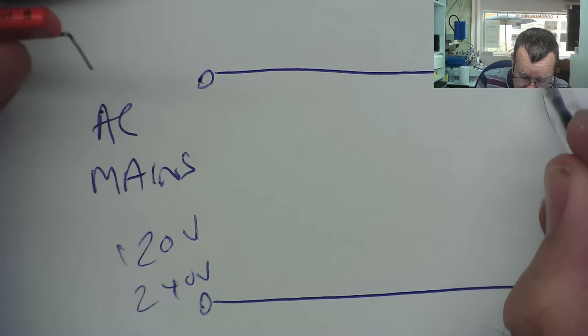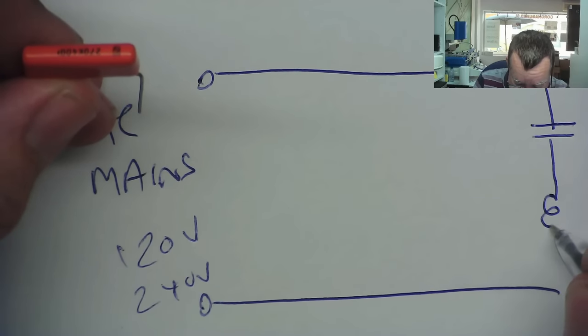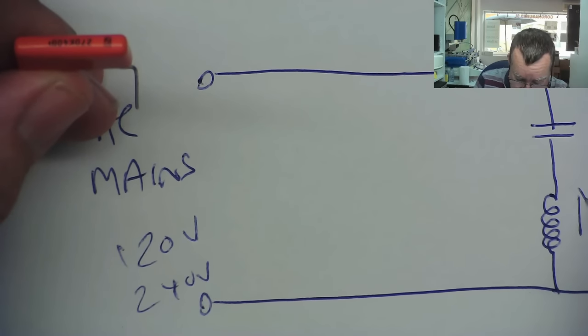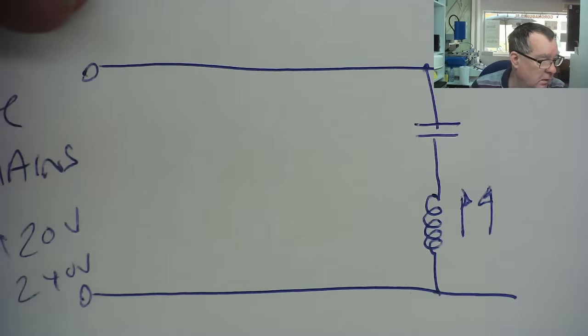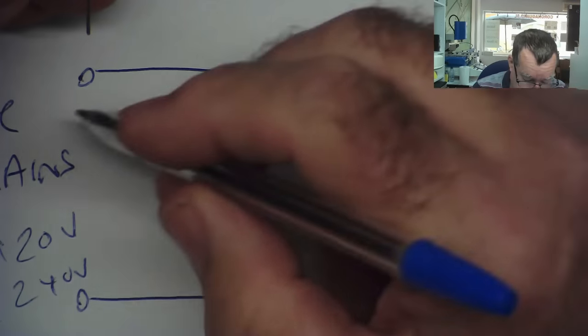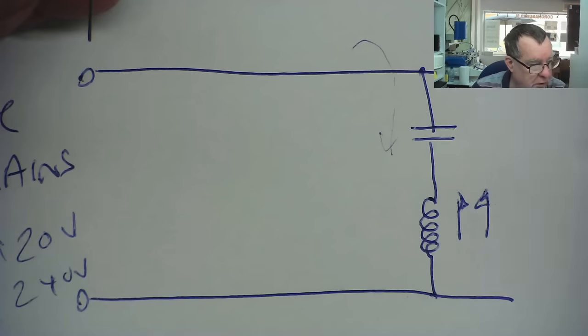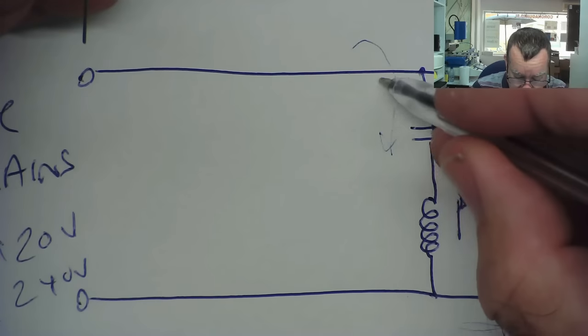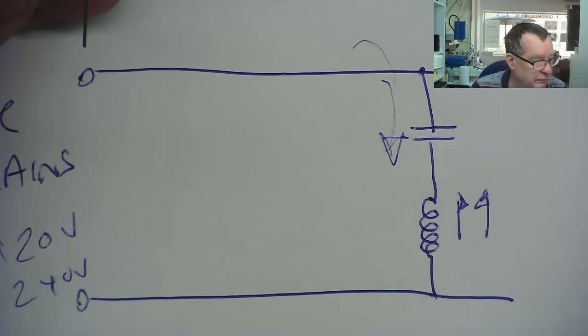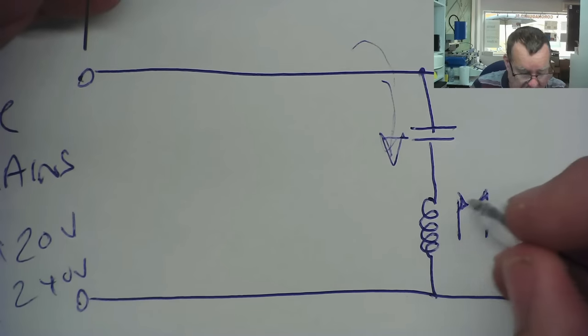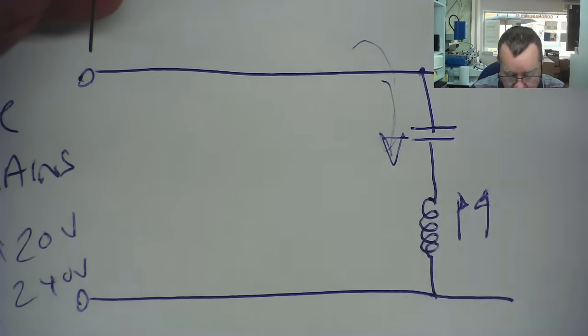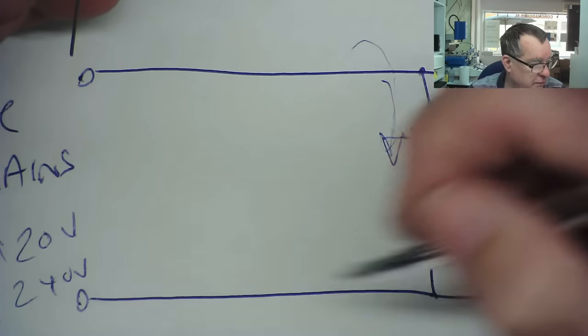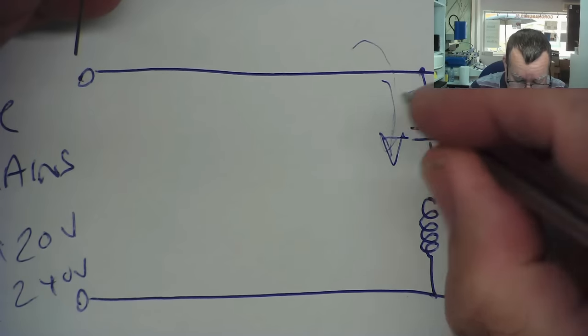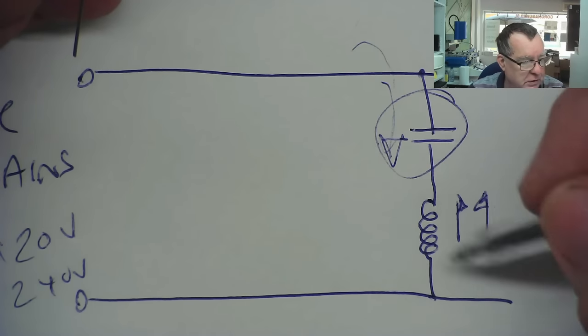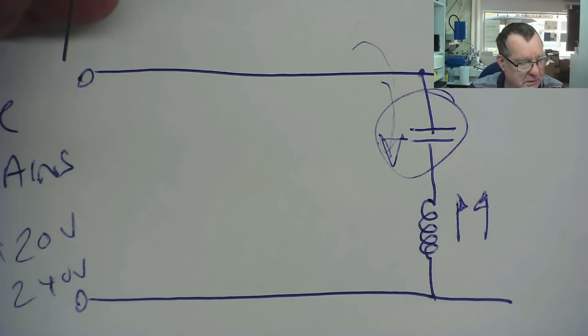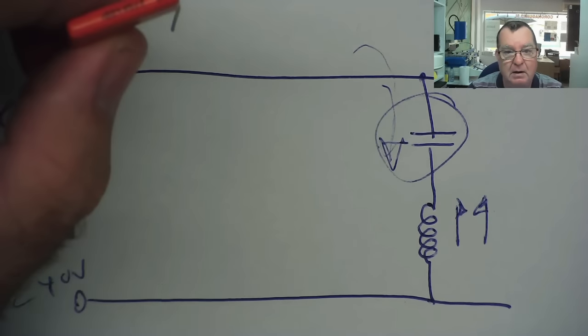The circuit had basically a capacitor like this one connected to a relay across here, and the relay had contacts. The idea was that the capacitor will block DC but pass AC. At 120 volts, there wasn't enough voltage coming through to turn the relay on. At 240 volts, there was enough voltage to turn the relay on, and that's how it detected the mains voltage. These contacts switch the voltage to the motors inside, the little AC motors, so that when you had a 240-volt supply, you got a reduced voltage going to the motors. This capacitor failed by going low capacitance, so it could no longer turn the relay on. Because it couldn't turn the relay on, it couldn't switch the voltage to the motors, so the motors burnt out. I've seen that a couple of times.